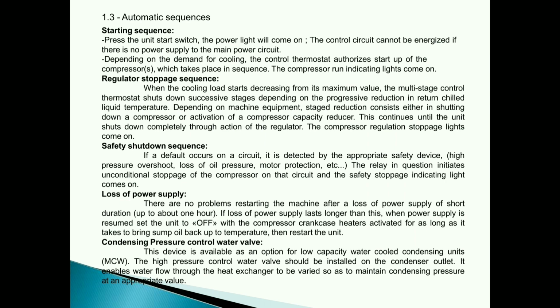Safety shutdown sequence. If a default occurs on a circuit, it is detected by the appropriate safety device: high pressure overshoot, loss of oil pressure, motor protection, etc. The relay in question initiates unconditional stoppage of the compressor on that circuit and the safety stoppage indicating light comes on. Loss of power supply.